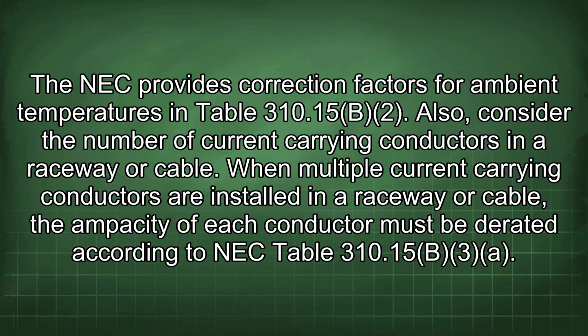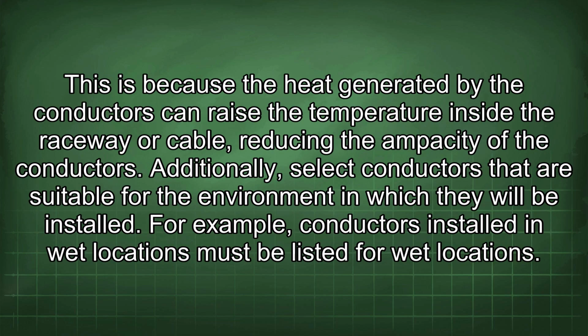When multiple current-carrying conductors are installed in a raceway or cable, the ampacity of each conductor must be derated according to NEC Table 310.15(B)(3). This is because the heat generated by the conductors can raise the temperature inside the raceway or cable, reducing the ampacity of the conductors.